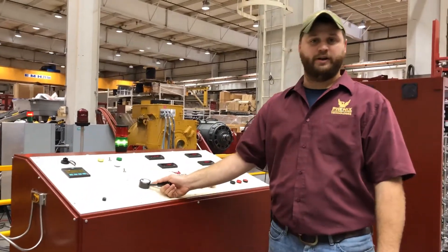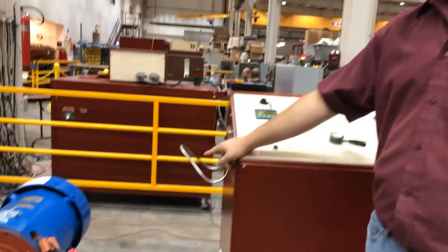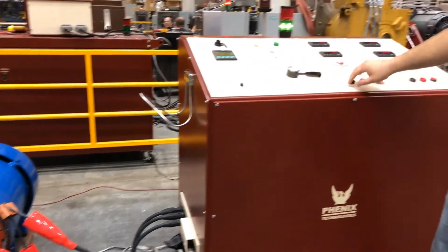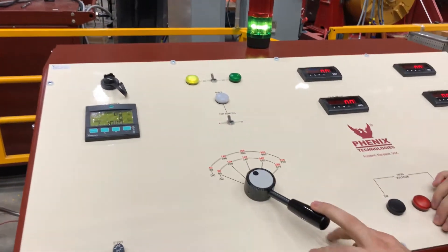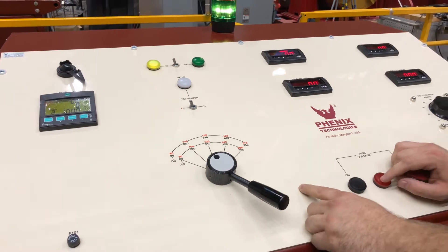This is the NCS100 NVD. We're going to be running a 550 volt motor with it. There are multiple taps to choose from. We'll be starting on a lower voltage tap to break the motor over and then working our way up to the run tap.